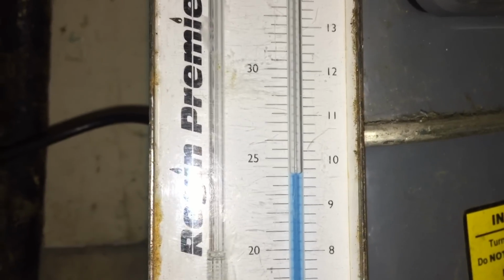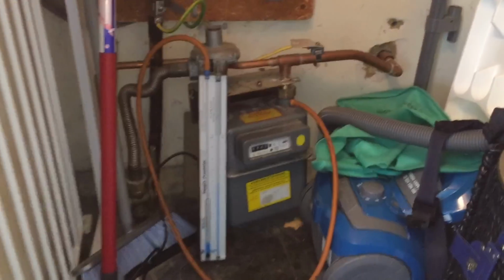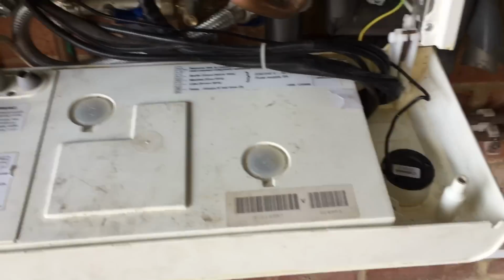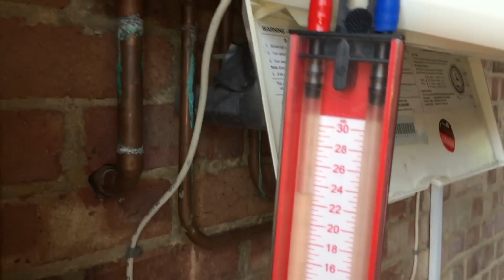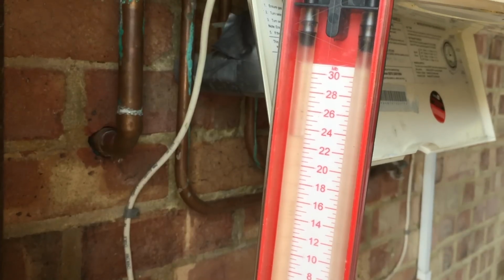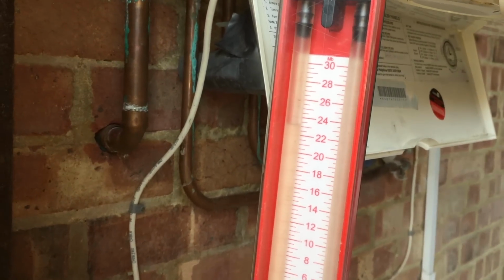Okay, so in and connected, back on, and we have a standing pressure of 24 millibar. So let's go reset that boiler and see what happens when it's trying to light. Okay, so turn it back on. You won't see it light because of the thing. At the moment we see this light, we'll go inside and see the gas pressure. Right, so that's lit. We'll go inside.